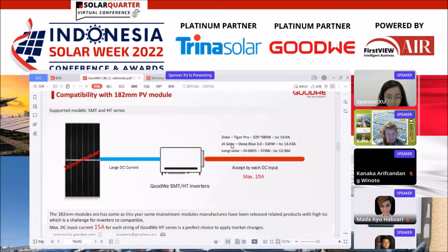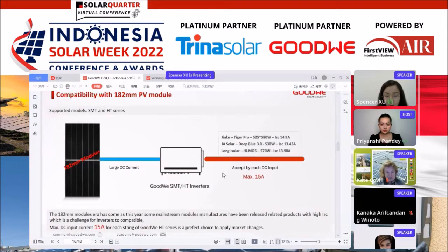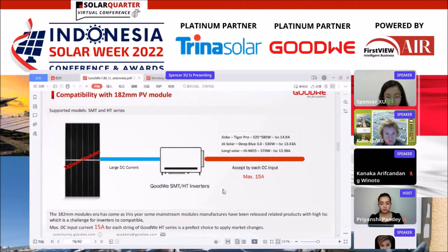So for the 182 mm PV modules, which is widely used in the utility scale power plants and also some commercial rooftops, our inverter can fully adapt to 182 mm PV modules. We can see that the mainstream 182 millimeter manufacturers have a short circuit current of about 13 to 14 ampere. And we found that even Jinko, which has a short circuit current of 14.9 ampere, is still below 15 ampere. And our inverter can support maximum 15 ampere input current. So we can say that we are fully compatible with the 182 millimeter modules.